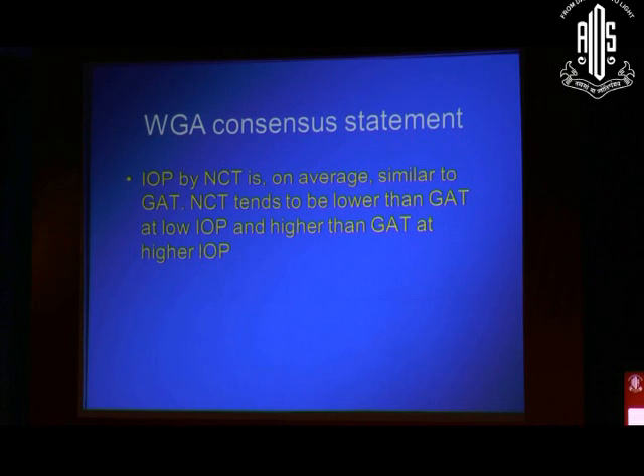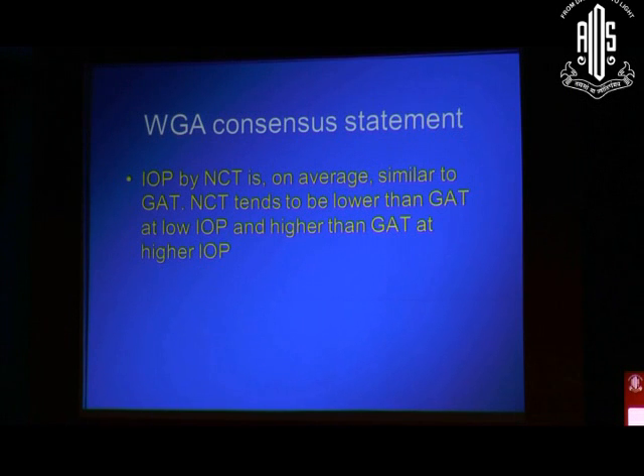So that is the amount of error you can expect between these two instruments on a routine basis. The World Glaucoma Association Consensus Statement says that intraocular pressure by non-contact tonometers is on average similar to that of Goldmann Applanation Tonometry — but that is on average, not for an individual patient. NCT tends to be lower than GAT at lower IOP, and tends to be higher than GAT at higher intraocular pressure. So you should be aware of this whenever you use the device.